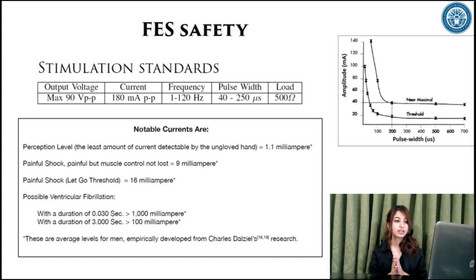The proposed functional electrical stimulation circuit is designed based on the human body stimulation standards for the FDA approved devices. It has been developed to match the device specification of EM41. The proposed circuit is superior to that of other devices and proposed circuits because it has the ability to digitally regulate its output voltage and the frequency automatically using the IMU feedback system. Moreover, the controller ensures that the pulses are out of phase by sending predictive electrical pulses based on the frequency extracted by the IMU feedback for optimum tremor suppression.